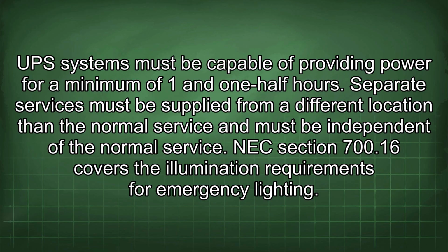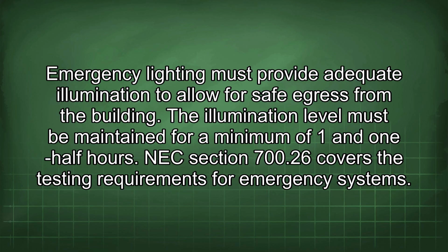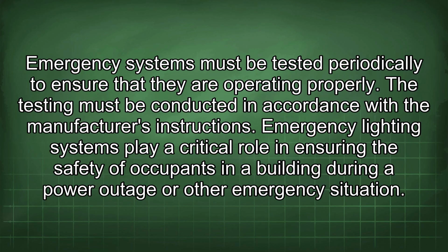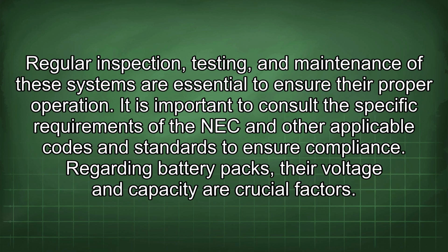NEC Section 700.16 covers the illumination requirements for emergency lighting. Emergency lighting must provide adequate illumination to allow for safe egress from the building. The illumination level must be maintained for a minimum of 1.5 hours. NEC Section 700.26 covers the testing requirements for emergency systems. Emergency systems must be tested periodically to ensure that they are operating properly. The testing must be conducted in accordance with the manufacturer's instructions. Emergency lighting systems play a critical role in ensuring the safety of occupants in a building during a power outage or other emergency situation. Regular inspection, testing, and maintenance of these systems are essential to ensure their proper operation.